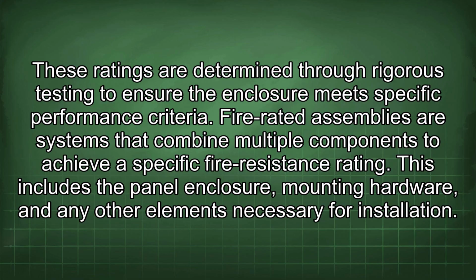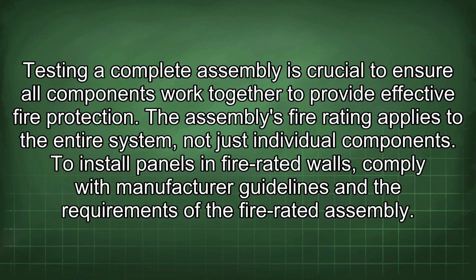Fire-rated assemblies are systems that combine multiple components to achieve a specific fire resistance rating. This includes a panel enclosure, mounting hardware, and any other elements necessary for installation. Testing a complete assembly is crucial to ensure all components work together to provide effective fire protection. The assembly's fire rating applies to the entire system, not just to individual components.